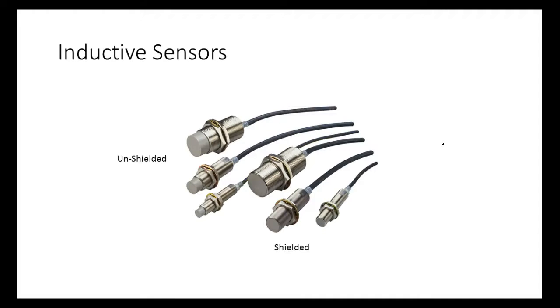So we have two types: shielded and unshielded. They look identical to each other, so this is something you have to keep in mind. You know, 'go in there and get me one of these' — they go trucking in there and say 'well, that looks like it,' and they give you an inductive sensor instead of a capacitive one or vice versa. That could cause you a lot of problems. So keeping those things separated, and also learning your part numbers, becomes very, very important.